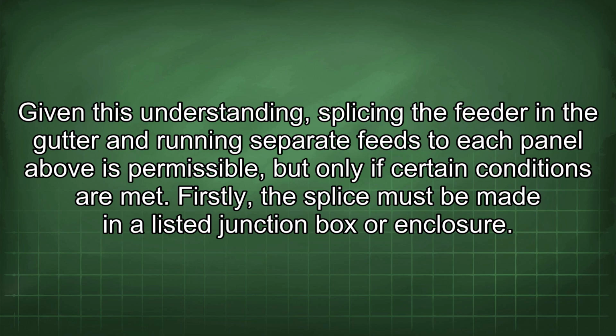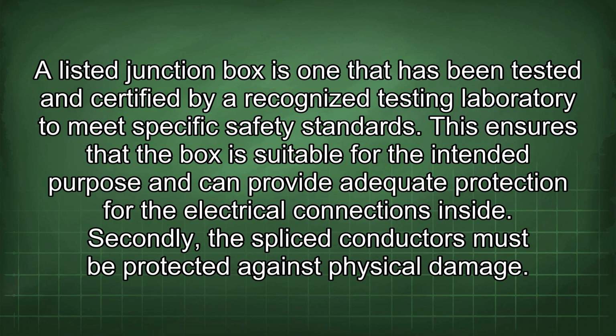Firstly, the splice must be made in a listed junction box or enclosure. A listed junction box is one that has been tested and certified by a recognized testing laboratory to meet specific safety standards. This ensures that the box is suitable for the intended purpose and can provide adequate protection for the electrical connections inside. Secondly, the spliced conductors must be protected against physical damage.